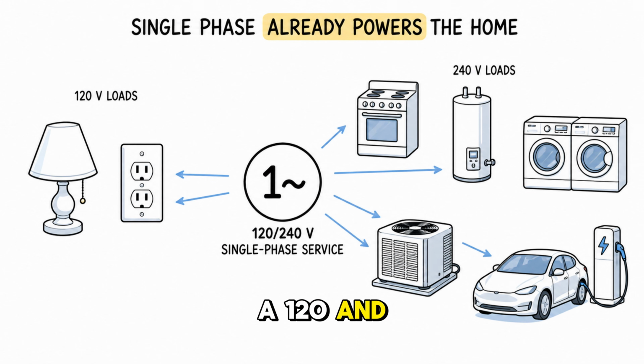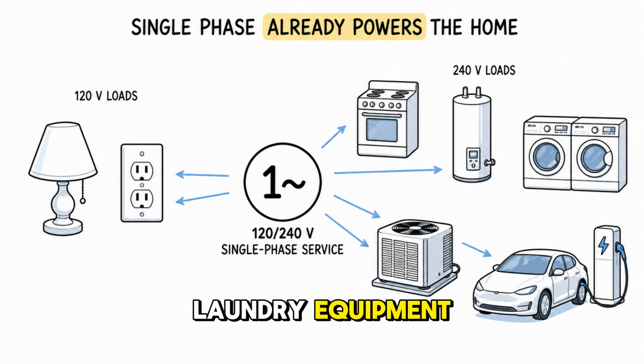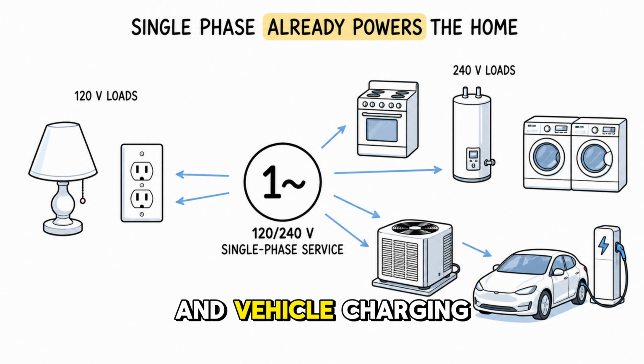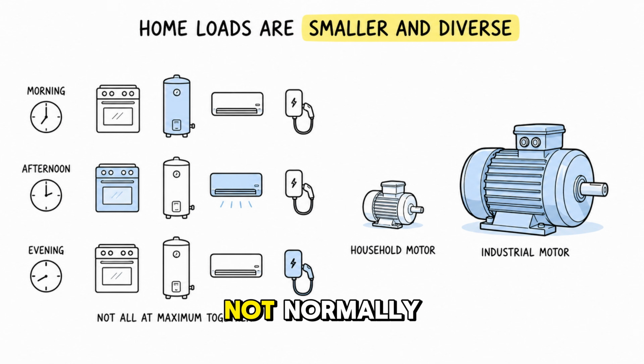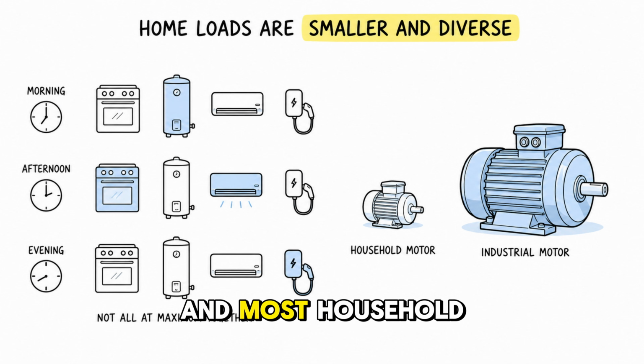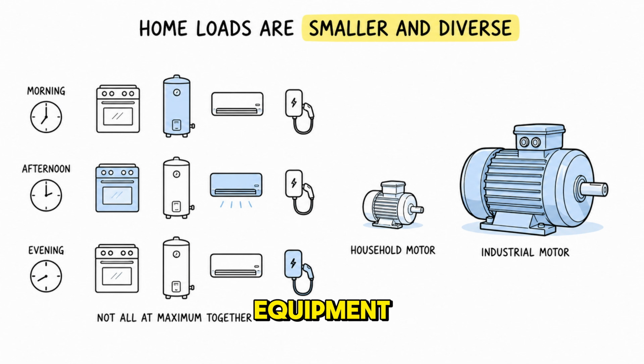A 120 and 240 volt single-phase service can already operate lighting, receptacles, cooking equipment, water heating, laundry equipment, air conditioning, and vehicle charging. These loads do not normally run at their maximum demand at exactly the same time, and most household motors are much smaller than the motors used in industrial equipment.